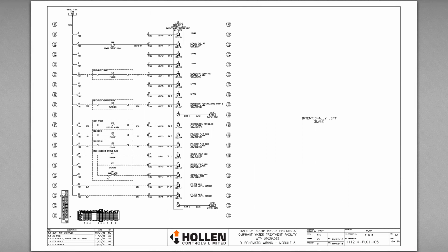Again, more IO. This is a DI card. You can notice here's another standard for how IO is wired. So if you have a panel with 3 IO points in it, the electrician could either run 6 wires out to it and run 2 back for each input, or run 4 out, 1 which would be common up to each one of the inputs, because electrically this is the same point, and then 1 back for each. So this is a good example that sometimes, even though you have 3 inputs, they might not have wires individually for each one. So it's good to see that. Does everybody understand what I said there?